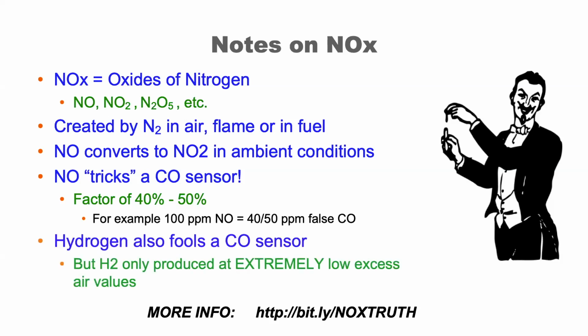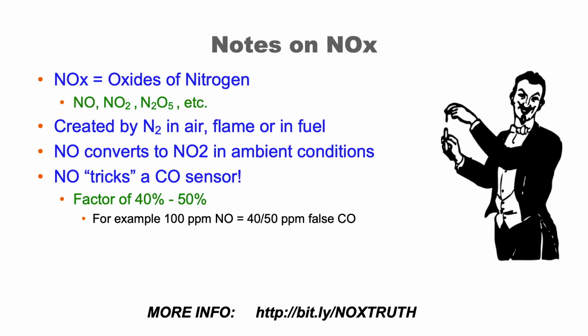The way around this is adding a NOx filter. You don't need to measure it, but you just don't want to measure it and think it's CO. We get a lot of questions with that. There are still some analyzers on the market that do not have nitric oxide filters, so they're going to report higher values. Then when you compare them to one that has the filter in it, you think, well, the one with the higher value's got to be right because it's sensing everything. The other one is wrong. Well, actually, it's the one with the nitric oxide filter that's correctly sensing only CO.